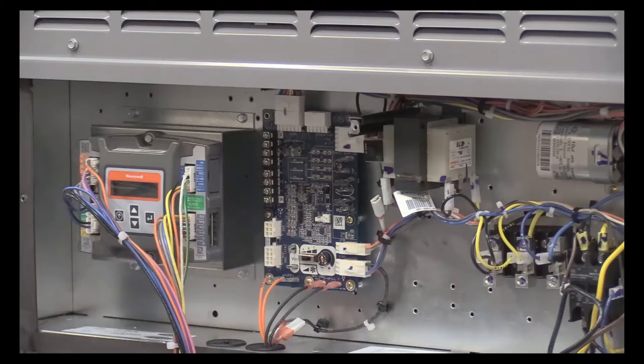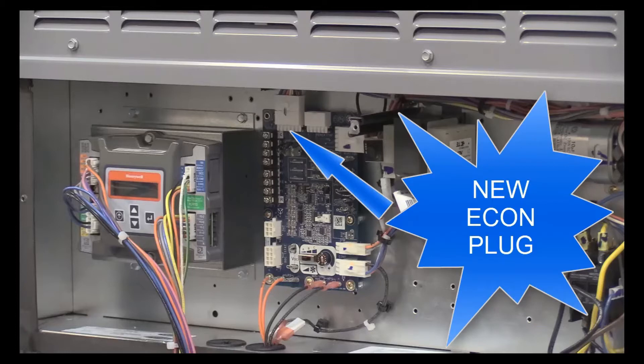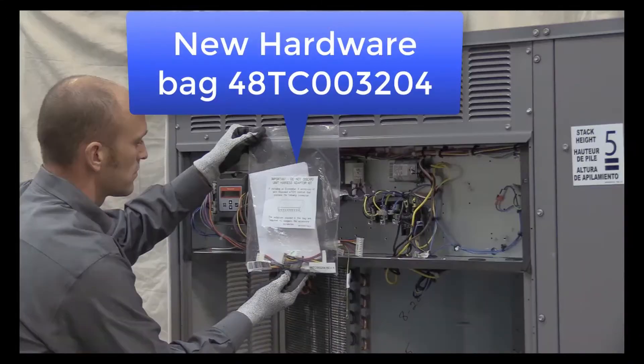This board has a new economizer plug, so the current wiring harness attached to the W7220 will not plug in directly. The electromechanical vane axial fan units that do not have factory-installed economizers include a hardware bag shipped in the control box that includes two jumper adapters and supplemental instructions. These adapters allow the current Jade Economizer harness to plug into the unit control board.